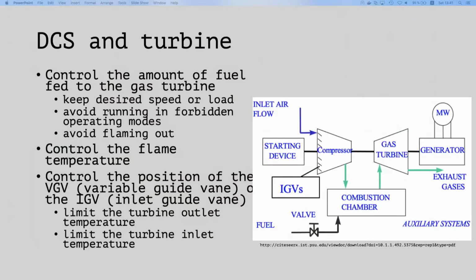For example, if we would like to answer the question of how we would regulate the output in megawatts of our power plant, we would need to control basically three things. Again, we are oversimplifying here. First, this is an example for the gas turbine: we would need to regulate how much gas we put inside the combustion chamber. We would control the flame temperature, and we would control the thing that gets air inside the turbine. Basically three things controlled by simple PLCs in the whole system, and you would be able, for example, to change 100 megawatts to 150 megawatts based on these settings.